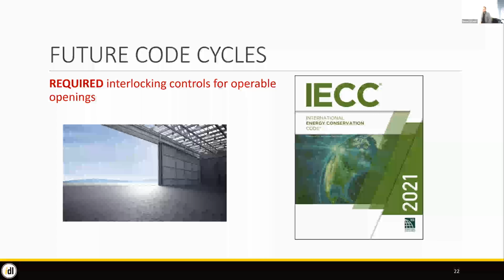The other new code requirement coming in 2021 is interlocking controls for operable openings. This would be very relevant if you've got big bays with trucks or equipment, or even a restaurant or coffee shop with those big roller doors. You can still have the roller doors, but if they're larger than 40 square feet, the system has to have some sort of feedback so you're not just air conditioning the whole street. Within 10 minutes of it being open, the cooling and/or heating will shut off, or at least have a very severe setback. It makes sense, but it's an extra set of controls you have to be aware of if you design an envelope that way.